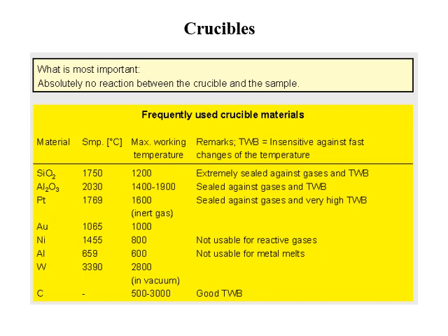The problem with platinum crucibles is they're very expensive, and TGA pans are actually very small, so they're damaged relatively easily. So you can spend a lot of money on platinum crucibles, but that's generally the preferred type. And obviously you want to make sure you're selecting a crucible that will not react with the sample itself.